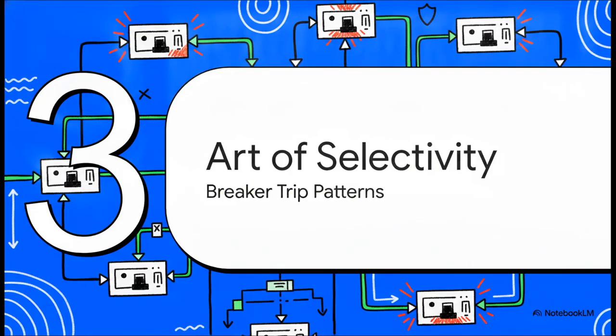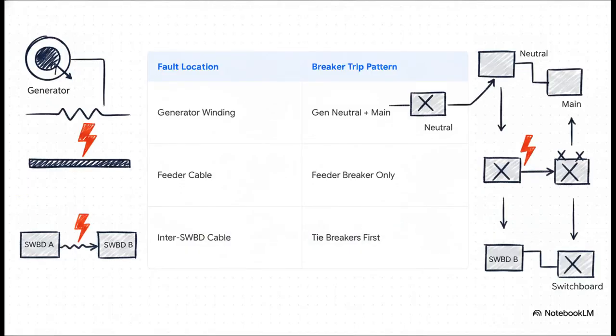Which brings us to the really critical part, the art of selectivity. Detecting the fault is one thing. Isolating it correctly is a whole different ballgame. And this brilliantly illustrates where true principled engineer skill comes in. Notice the strict rules of isolation across 3 distinct fault locations. We're looking at 3 totally different breaker trip patterns here. If a fault happens inside a generator winding, the system absolutely must trip the generator's neutral point breaker and its main breaker immediately. That isolates just that specific machine.